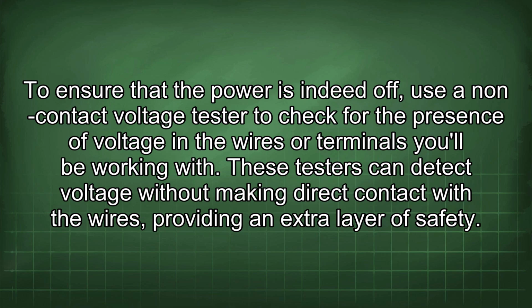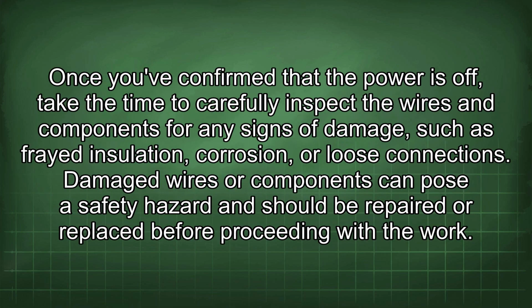To ensure that the power is indeed off, use a non-contact voltage tester to check for the presence of voltage in the wires or terminals you'll be working with. These testers can detect voltage without making direct contact with the wires, providing an extra layer of safety. Once you've confirmed that the power is off, take the time to carefully inspect the wires and components for any signs of damage, such as frayed insulation, corrosion, or loose connections. Damaged wires or components can pose a safety hazard and should be repaired or replaced before proceeding with the work.